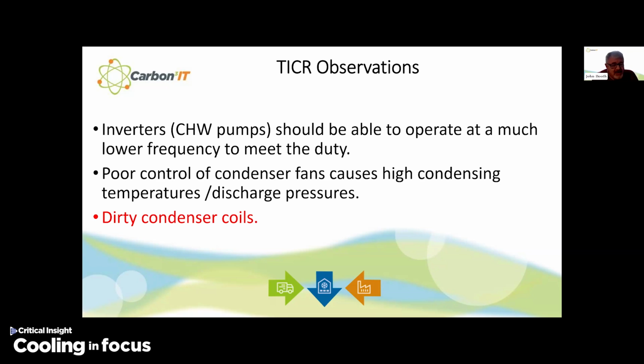Now, this is a really easy win, right? If your air conditioner is not functioning as it used to, get up there and clean the coil, the external plant. Now, don't clean it from the outside in. You should look at your coil O&M manual and see how the manufacturer says you should be cleaning it. Invariably, with a V-shaped chiller or coil, you should be working from the internal part of the V and cleaning against the airflow.